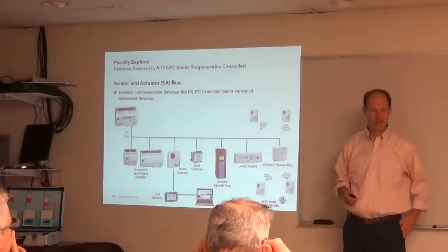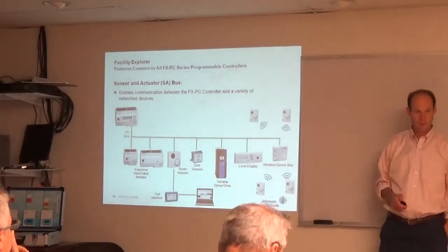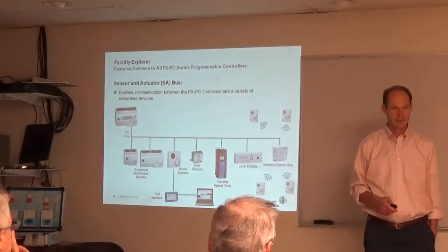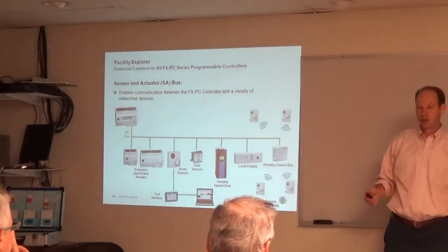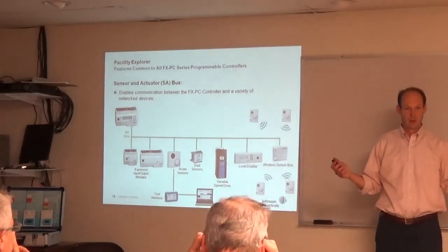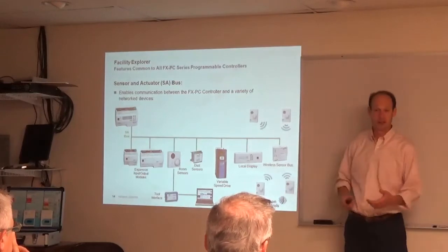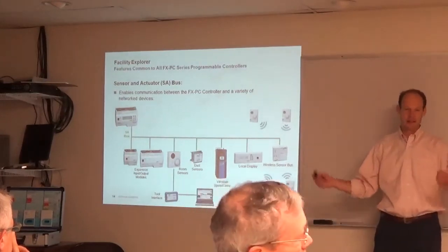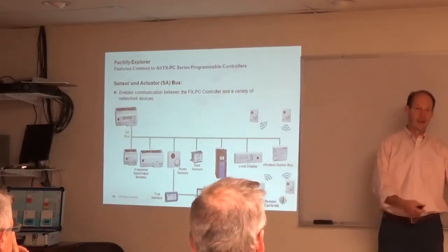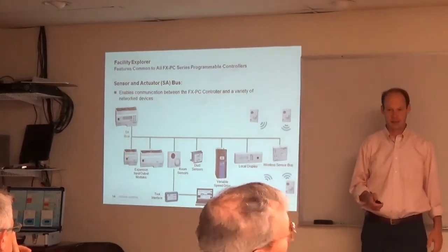It's up to you to use it and map it. What happens if the battery does go dead to the temperature in the room? You would get an alarm saying, guess what, I don't have zone temperature anymore. Does it default to something? Whatever you put in as a default. You can put in any internal controls, you can put a default value in there, and guess what, yes. I lost my zone temperature, I'm going to default to 70 degrees, and alarm, change your batteries. I lost my sensor.